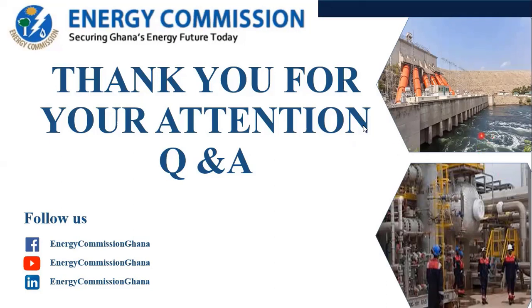Mr. Rashid, this is something I have encountered with some electricians. Sometimes I just laugh at them. They just go and buy any RCD at all and come and fit it. There was a situation where they bought the wrong RCD and installed it in a church, and it kept tripping because they didn't size the RCD to meet the load of the church. The church itself had no problem, but because the RCD sizing wasn't matched to its load, it kept tripping.